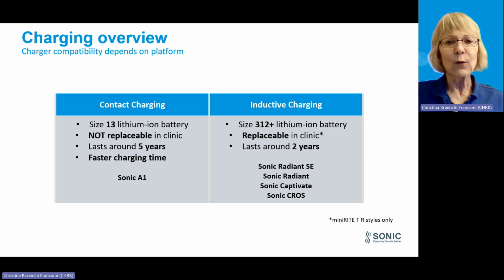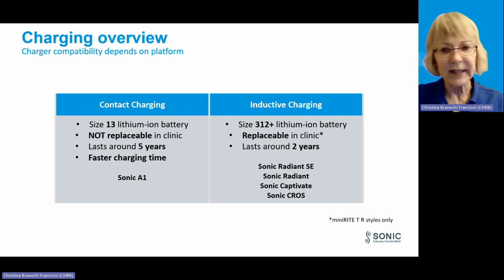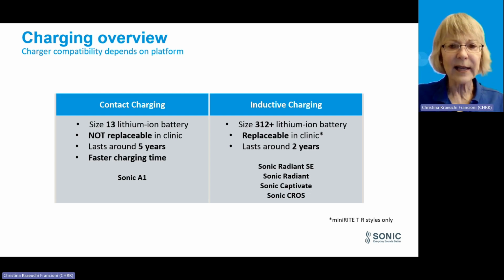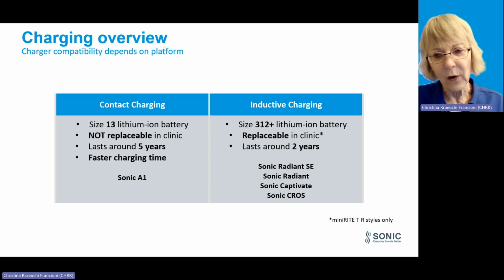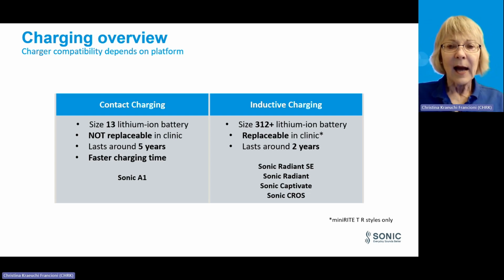Inductive charging for hearing aids uses transmitting coils in the charger and receiving coils in the hearing devices. In the Mini Rite TR, Mini BTE TR, and CROS styles, the antenna coil acts as the induction coil. When the instruments are inserted into the charger's charging ports, the hearing aid's receiving coil is positioned very close to the charger's transmitting coil. This allows the creation of an electromagnetic field between them. The electromagnetic field permits electric energy to be transferred from the charger's transmitting coil to the hearing aid's receiving coil. The hearing aids use the transferred electric energy to rapidly recharge its internal lithium-ion battery.